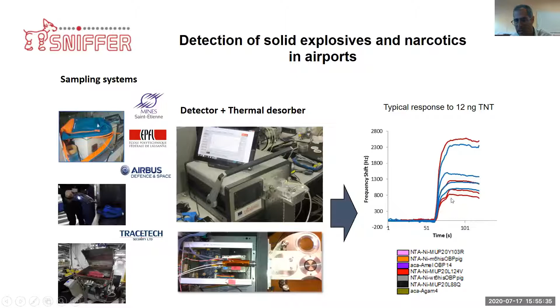And here we are looking at a typical response for 12 nanograms of TNT, which is of course an explosive compound, when it is exposed to our sensor array, which contains a range of MUPs and OBPs. And you can see that we have a high sensitivity. 12 nanograms is typically what we're trying to achieve in the real applications. So we are meeting this target. And you can see again that each sensor has a different sensitivity to the same TNT analyte in this case.